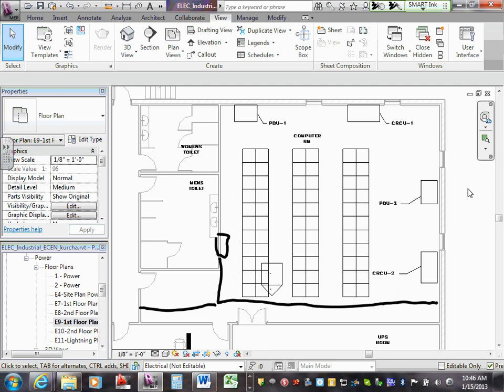When you guys have a data center computer room, there are 2 types of smoke detectors that you're supposed to have. One type will be in the ceiling, and the other type is under the raised floor. So the one on the ceiling, I don't know if we're going to talk about that one, if it's required or not. But what he's talking about right now is when they raise the floor and they put all these racks full of computers, and underneath it they put smoke detectors or that Vesda system, which is set with pipes, plastic pipes with a compressor, right? And it samples the air. It's sampling the air and it's a smoke detector. So there are 2 systems. Be aware that one thing is the smoke system underneath that. Yeah, it will be. Yeah, usually they have a couple of CRAC units forcing the air through there. What requires you to have the protection underneath is all the cables and any combustible material.